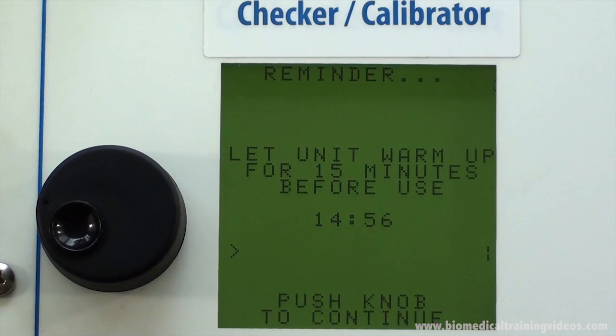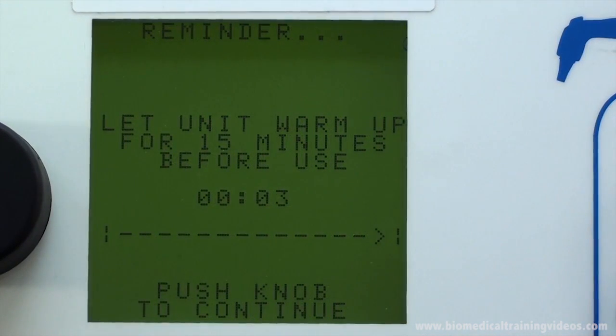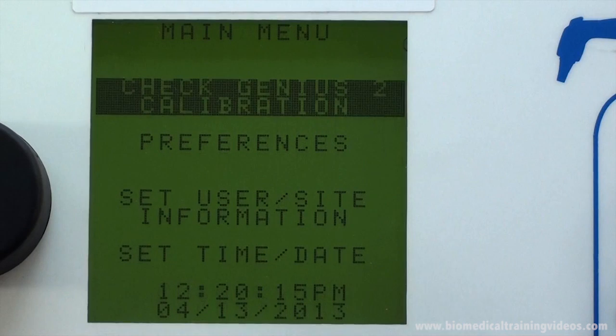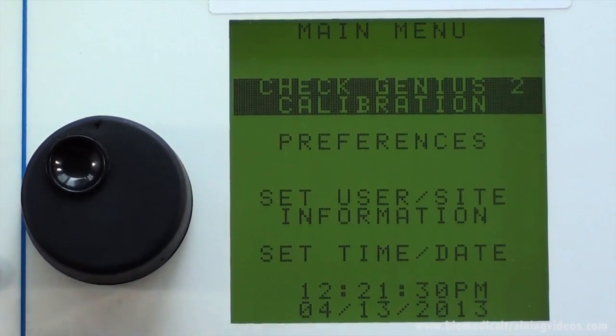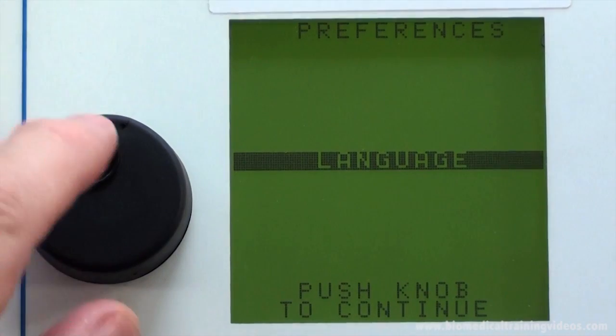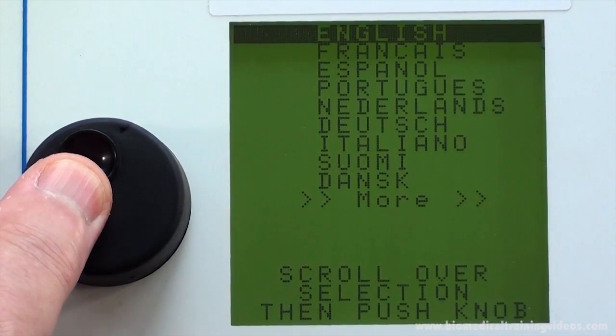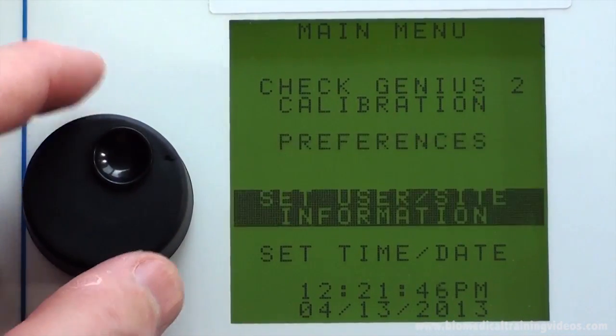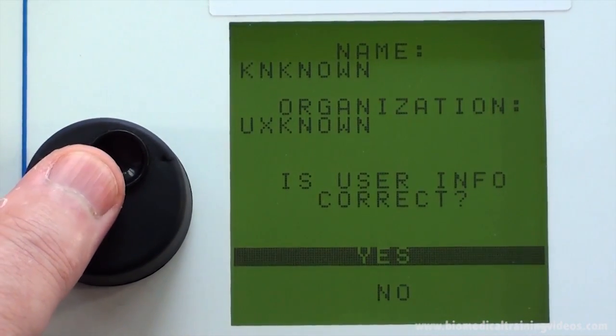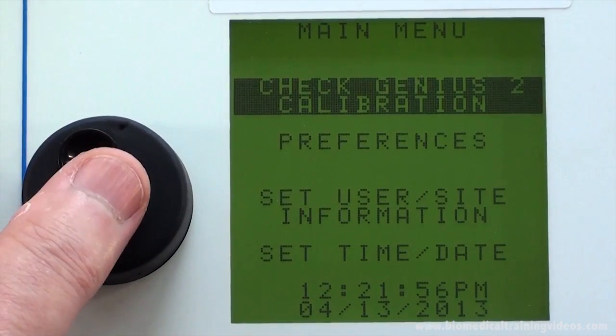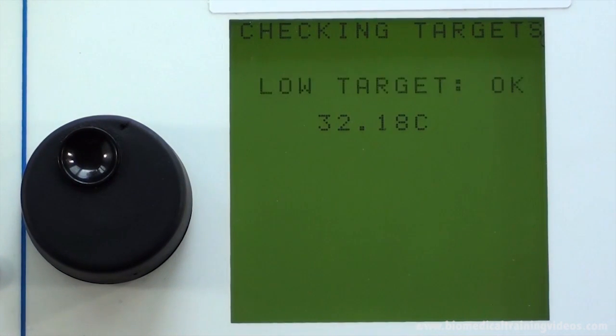So when it's first turned on, you get a message saying that you should allow 15 minutes to warm up. This is to make sure the targets are stable. So once that 15 minutes is up, we can continue on. Just again looking at the main menu, got some preferences, which is really just language. You can also set the site information if you're doing reports and that sort of thing. It's useful. Time and date, of course. So here we are, just making sure the targets themselves are stable and within specification. As you can see, the low target is about 32 degrees and the high target just over 40 degrees.